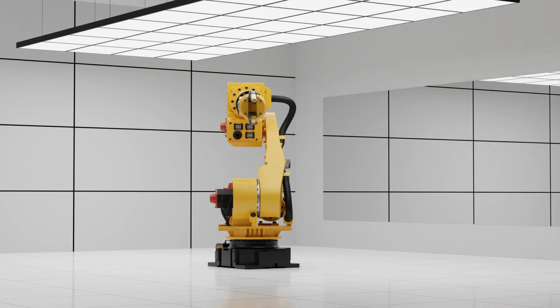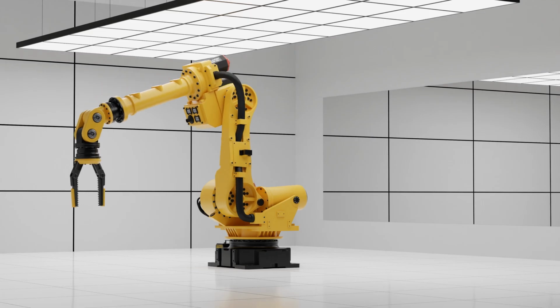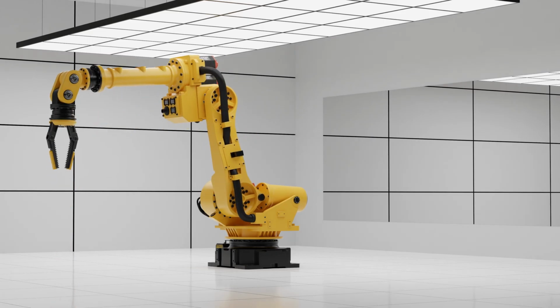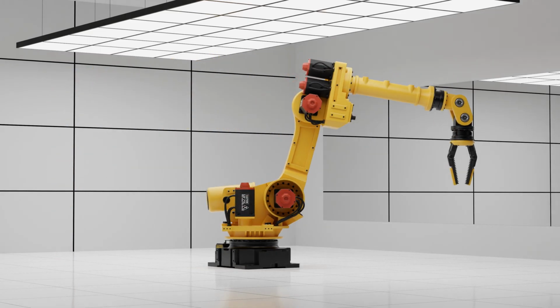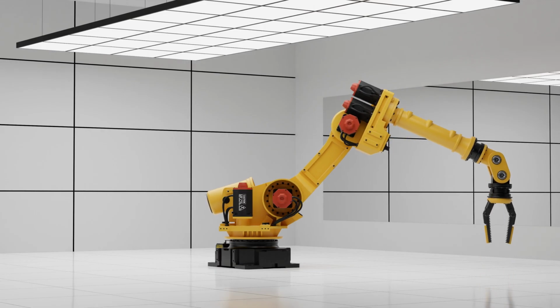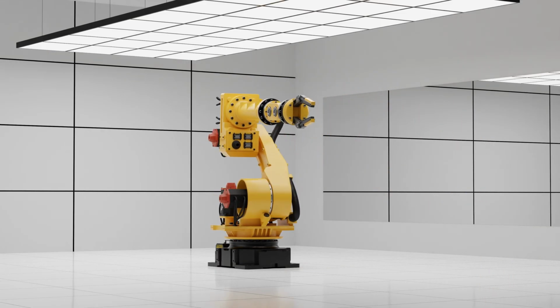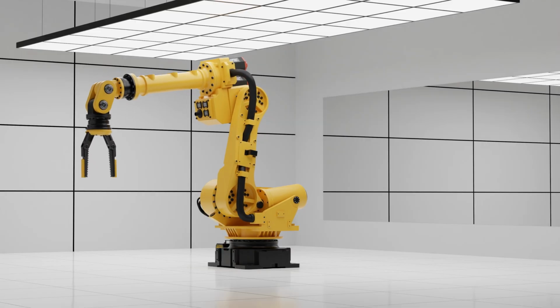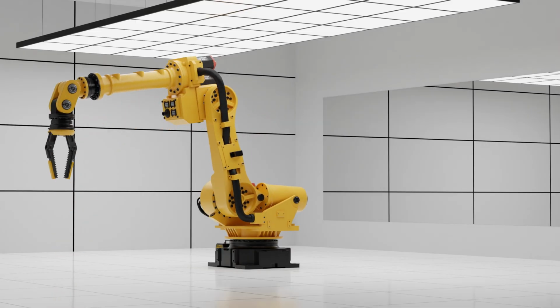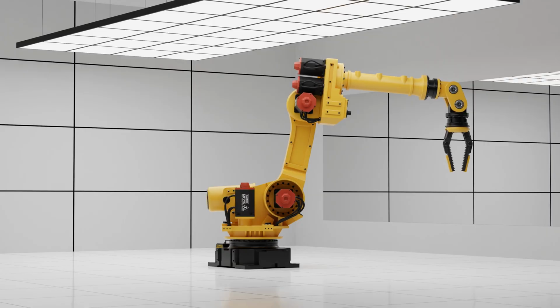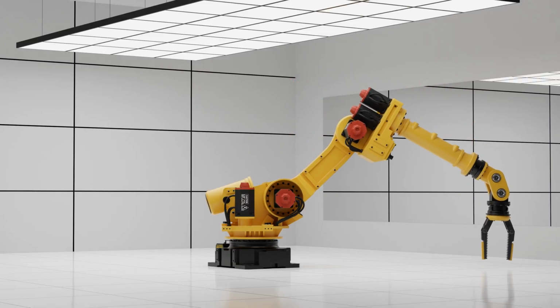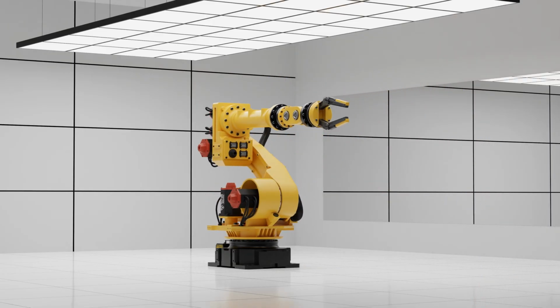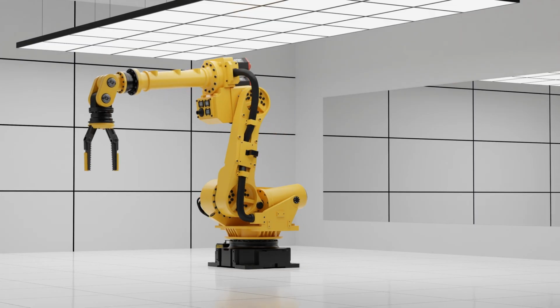But I'm guessing there is a catch. The catch is that dry towers are significantly less efficient, especially in hot climates. If you build a data center in Arizona, blowing 100-degree ambient air over a dry tower radiator isn't going to cool your servers down very well. You have to use massively powerful fans, which means you are spending a fortune on electricity just to run the cooling system.